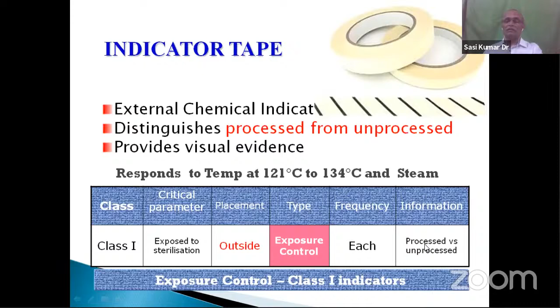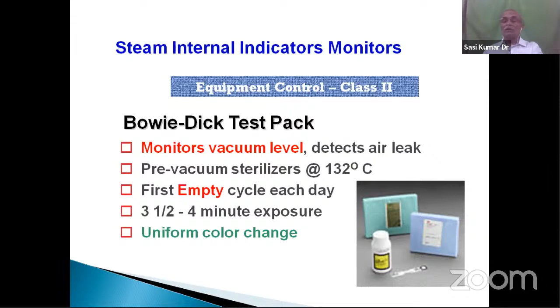It comes as a roll and it is affixed on all the packs, but it just mentions whether the pack is processed or unprocessed. This is a class 2 indicator, otherwise called a Bowie-Dick test pack, which is used to assess the amount of vacuum that is created in the sterilizer, the autoclave.